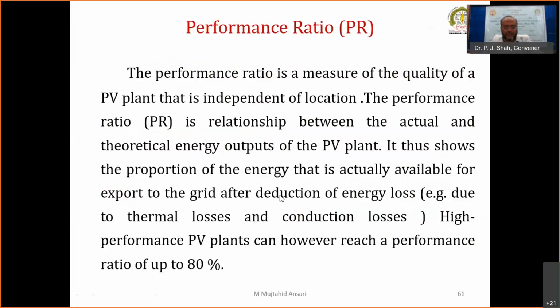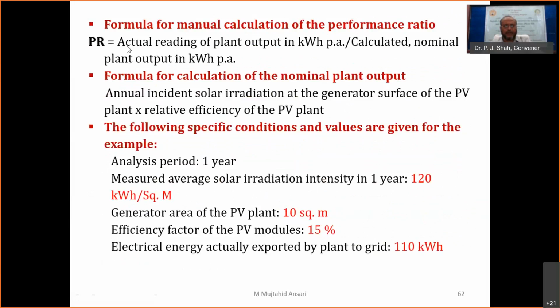So what is the performance ratio? The performance ratio is calculated by this formula: actual energy generated per annum divided by nominal plant output. The nominal plant output is the annual solar irradiation at the generation surface of the plant multiplied by the relative efficiency of the PV modules. For example, consider a 1 year analysis. Measure the area available for the PV modules. Then the generation area of the PV modules is 10 square meters. The efficiency factor of the PV module is considered as 15, and the total energy exported to the grid is 110 for the given data.